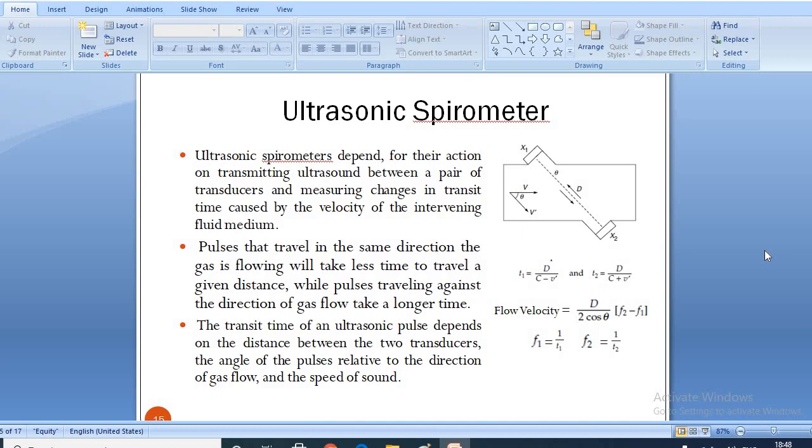The flow velocity is found to be D/(2 cos θ) × (F2 - F1), where F1 = 1/T1 and F2 = 1/T2. The transit time of an ultrasonic pulse depends on the distance between the two transducers, the angle of the pulses relative to the direction of gas flow and the speed of sound.